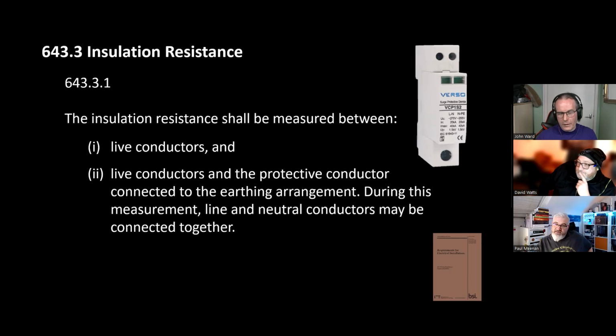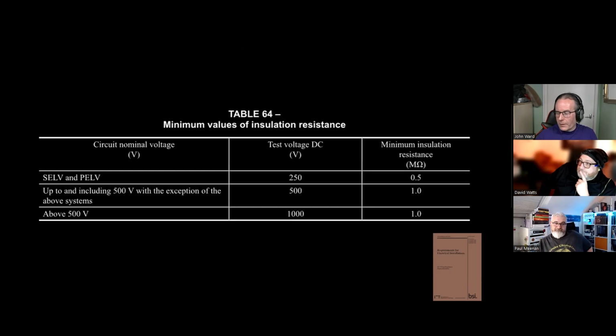You don't want to be blasting that thing. And if you do try to test with it there, it will just give you a zero result anyway, so you'll know pretty much straight away that something is not right. This is table 64, your minimum values. For any normal installation, it's 500 volts and a 1 megohm minimum resistance, not 250 as the main one. You can use that in some cases, but you need to test at 500 unless it's one of the others in the table there.